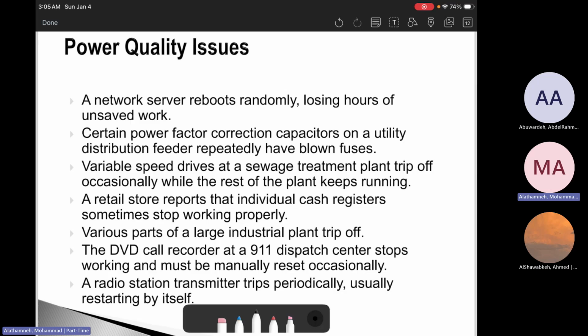And the other thing is the radio station transmitter, which can trip periodically, restarting itself because of the power quality issue. So engineers must translate complaints into a proper power quality phenomenon. That's the skill: complaints, waveform events, source. We need to mitigate it and try to solve it as much as possible.